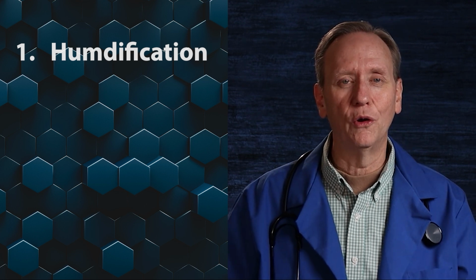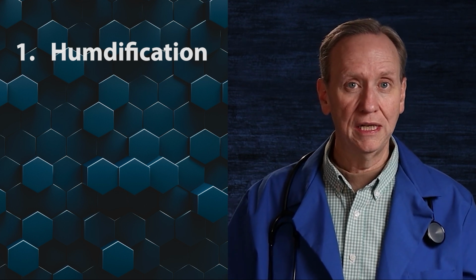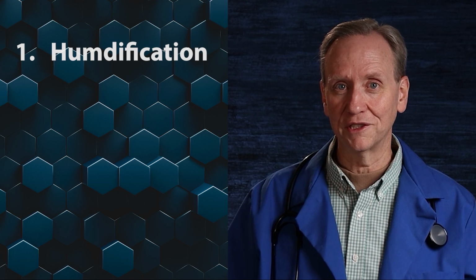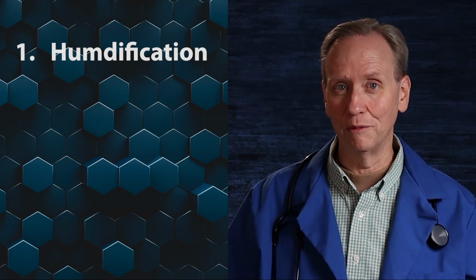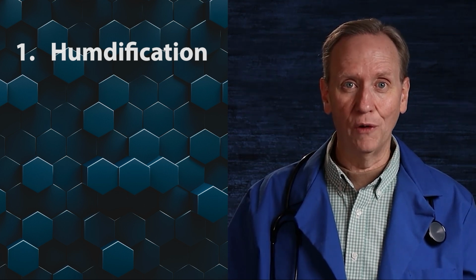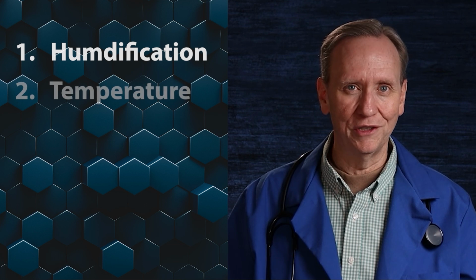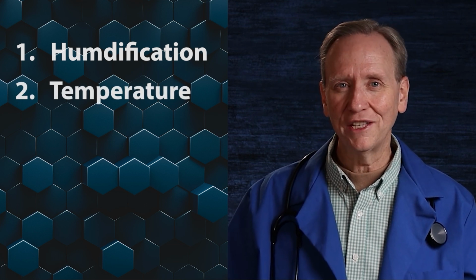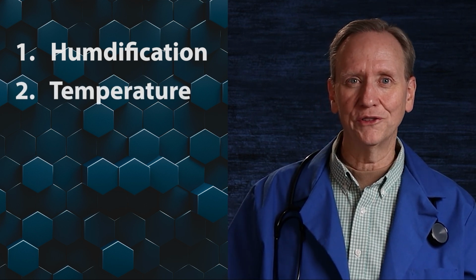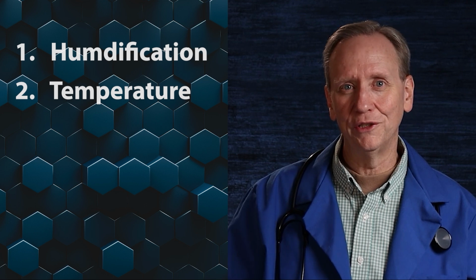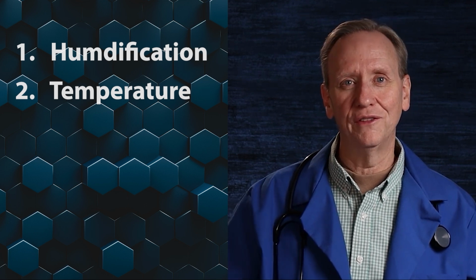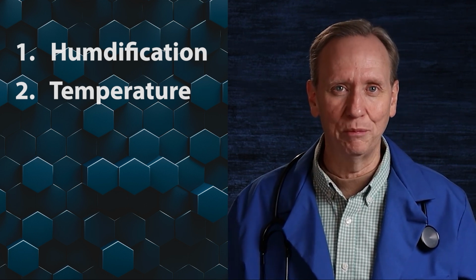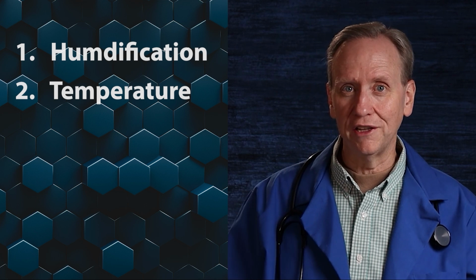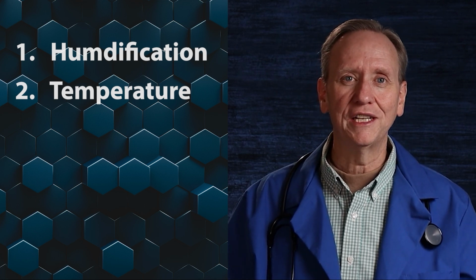All right, and so we're going to have to humidify the gas. Well, it's not easy to humidify gas that's going at 50, 60 liters per minute. And so to do that, we need to increase the temperature of the inspired gas. And so that's going to be another setting. Instead of only setting the flow, you're also going to be setting a temperature.